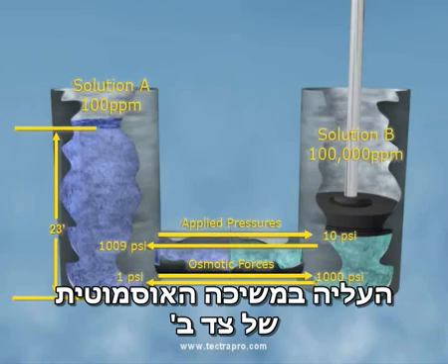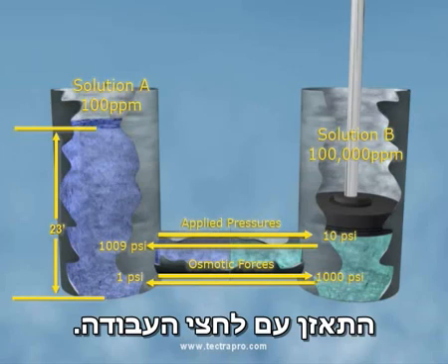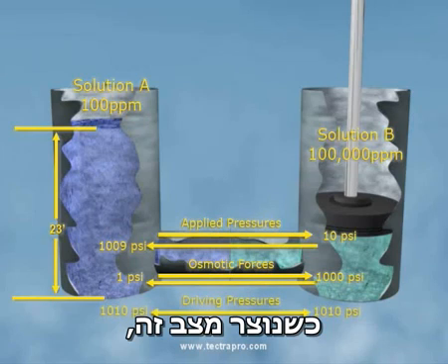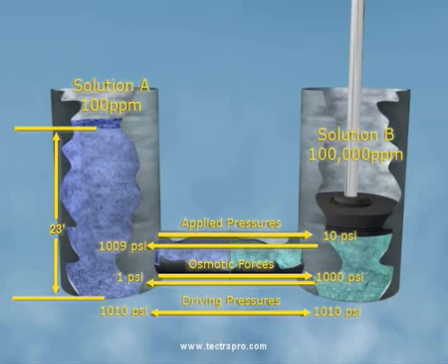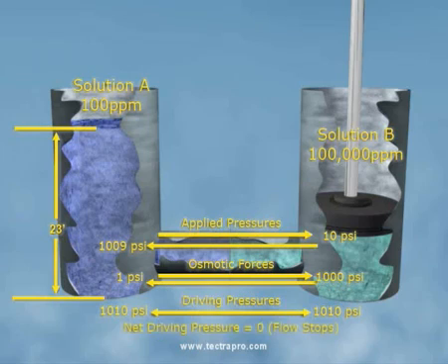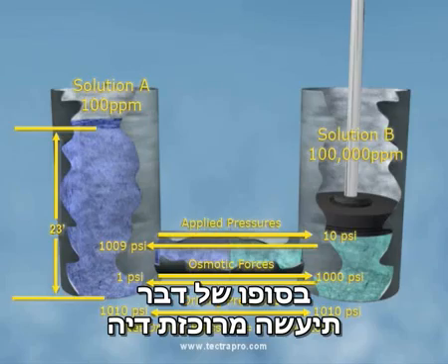The increased osmotic attraction of side B combined with the increased hydrostatic head of side A has evened out the driving pressures. When this condition has occurred, the net driving pressure has become zero. This illustrates the need for reject flow. Any solution, no matter how diluted, will eventually concentrate enough to shut down a reverse osmosis system.